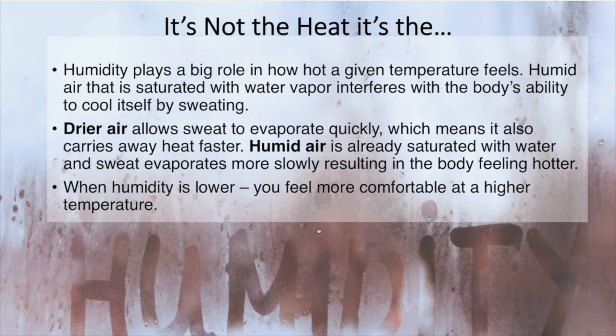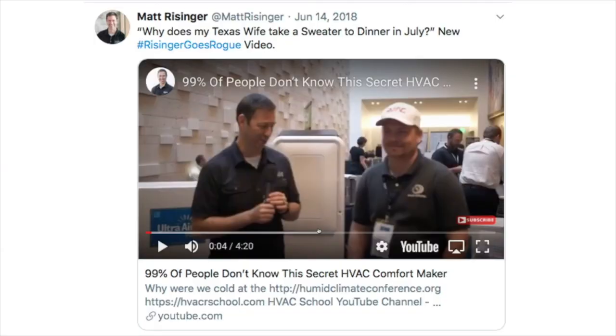And the key to this is when humidity is lower, you will feel more comfortable at a higher temperature. So in reality, if you do have 50% relative humidity in a home, you should feel much more comfortable at 78 degrees on that thermostat. And people who do get dehumidifiers are surprised, if they haven't changed their thermostat setting from, let's say, 74 degrees, how cold they feel with that dehumidifier keeping it to that 50-55%, and they increase their thermostats. Matt Risinger did a really great video titled "Why Does My Texas Wife Take a Sweater to Dinner in July?" that I highly recommend, and he talks about basically overcooling to dehumidify.